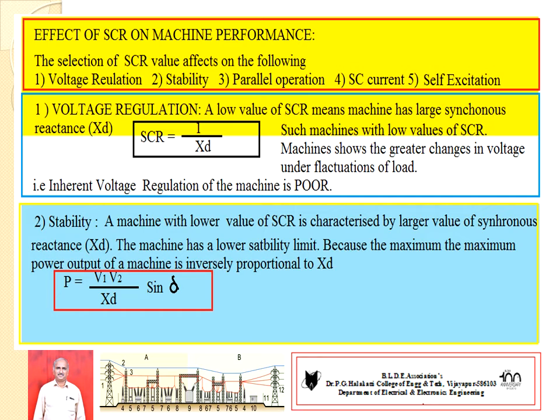Number two: Stability. In a power system, the power transfer between any two points is given by: P = (V1 × V2 / XD) × sin(δ), where V1 and V2 are voltages between the two points and XD is the direct axis reactance. Maximum power transfer gives good stability. However, at a lower value of SCR, a higher value of synchronous reactance is developed, so the machine possesses a lower stability limit. Since maximum power output is inversely proportional to XD, a low SCR leads to low stability.